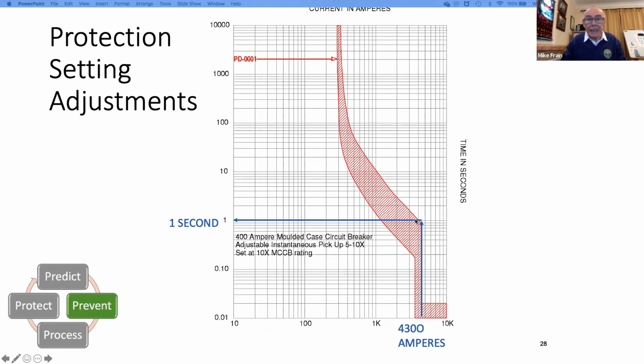In this particular case, it's got instantaneous pickups which are adjustable between 5 and 10 times, and it's set at 10 times the rating, so at 400 amps, it's set at 4,000 amps, the instantaneous setting. But what we've got here is an arcing fault, which is 4,300 amps. So taking into account the protective device settings and so on, that will disconnect in 1 second. So the fault will persist for 1 second.